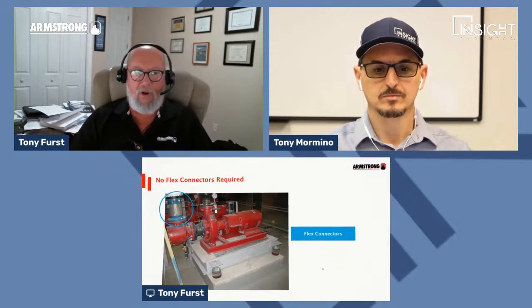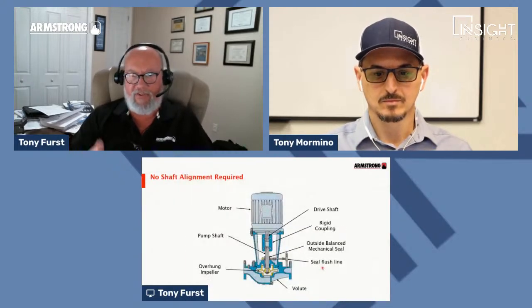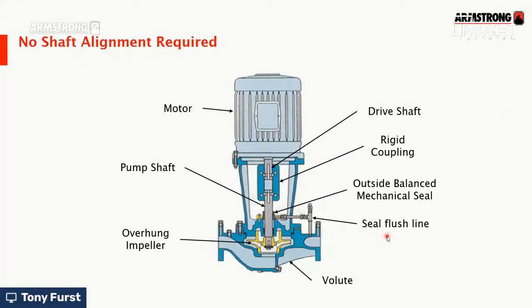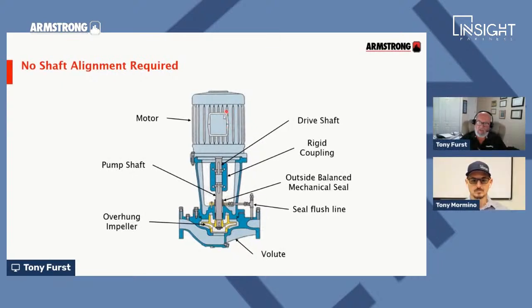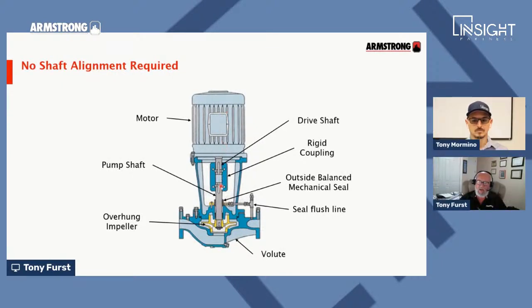So now we talk about a pump shaft, and this is a nice cutaway of a vertical inline pump. Okay. So up here at the top, we have our motor. Everybody can see the motor, and then we come down and we have a coupling, and this is what's known as a split coupled pump as opposed to a close coupled pump. And there's two different types of vertical inline pumps. There's a split coupled, which is what you see here, and the close coupled. The difference is the motor is set closer to the impeller, and the motor shaft is directly connected to the impeller. Whereas a split coupled it's two different shafts that are coupled together by a rigid split coupling.